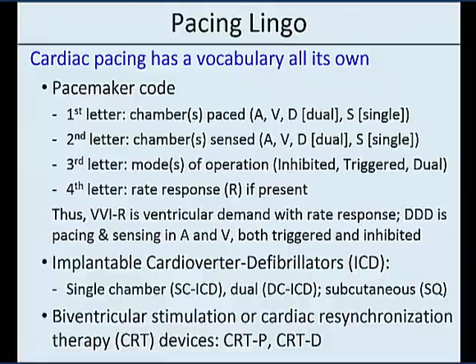programmed mode. Implantable defibrillators, or ICDs: now there is a brand, Boston Scientific has a brand called the Automatic Implantable Cardioverter Defibrillator, AICD. That's a brand name, so if somebody has a different manufacturer's device, it's just an ICD. There are single chambers, dual chambers, and we used to call a single chamber an SCICD. Well, now there's a subcutaneous ICD, so people call that an SQ or an SC. That causes some confusion, but now one manufacturer makes a subcutaneous one with no leads inside the heart, with some particular advantages there. Biventricular stimulation is possible nowadays, and as a cardiac resynchronization therapy device, they can be both pacemakers, or a pacemaker pacing function in a defibrillator can.